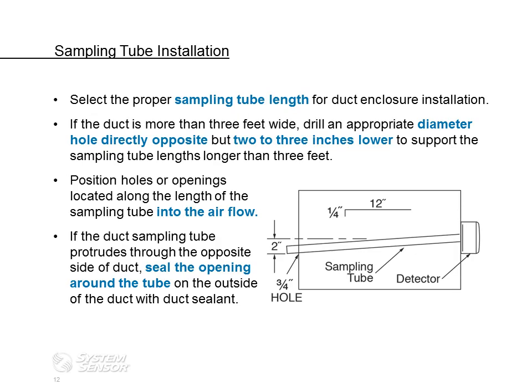How do we install the sampling tube? First of all, we have to select the proper sampling tube length for the duct enclosure. If the duct is more than 3 feet wide, you may have to drill an appropriate diameter hole directly opposite, but 2 to 3 inches lower to support the sampling tube length longer than 3 feet. The standard says that if a sampling tube is greater than 3 feet, it has to be supported.